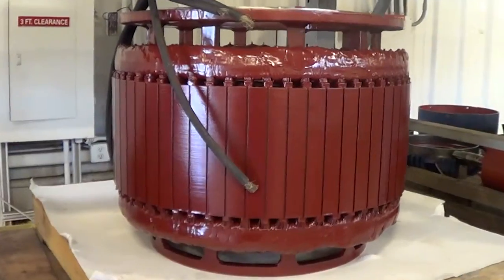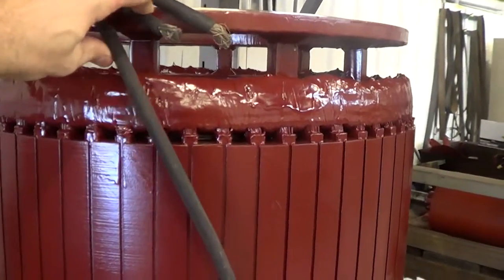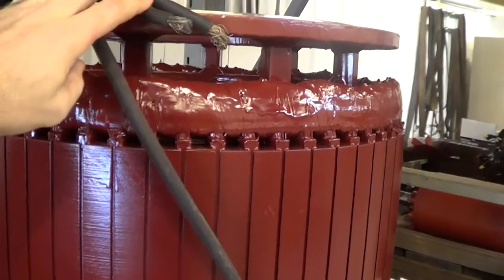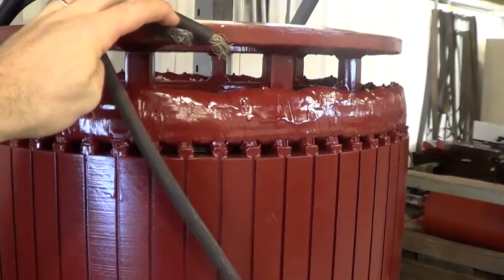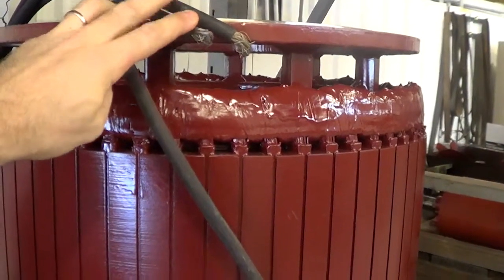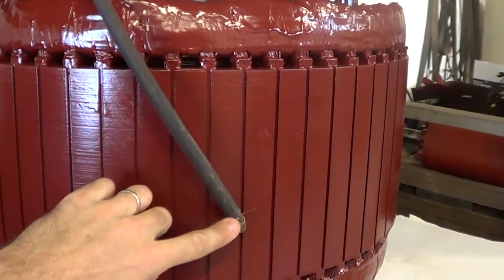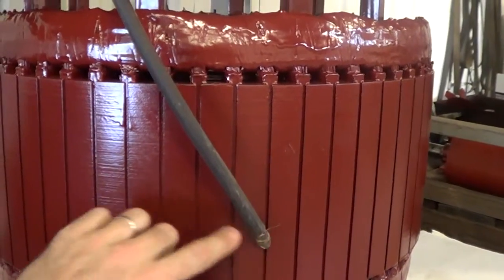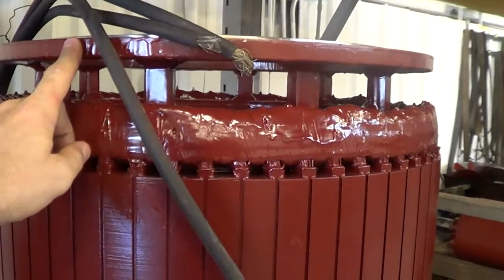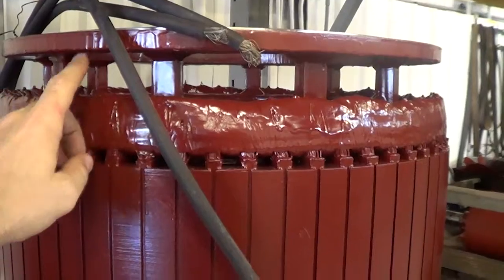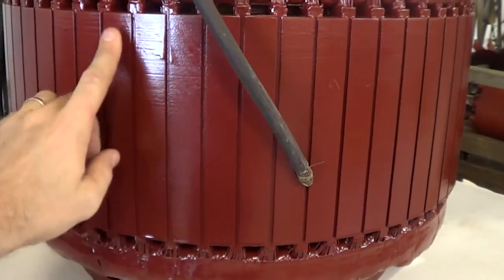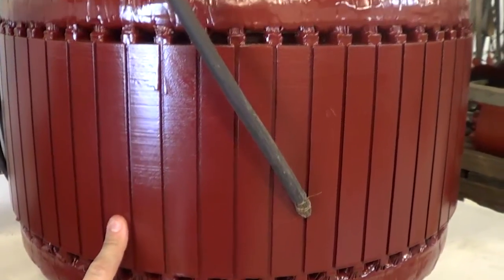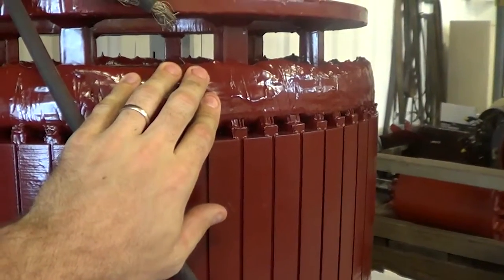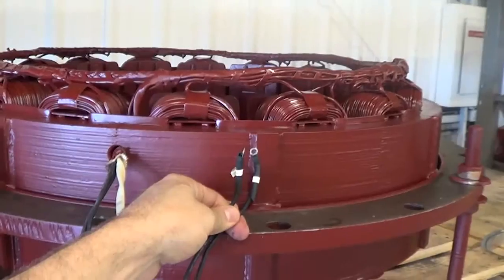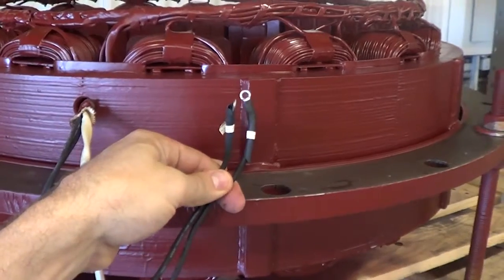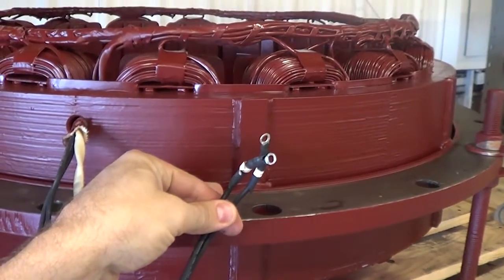The exciter rotor includes a 3-phase winding with 3 leads. Check the resistance using a digital low resistance ohm meter or micro-ohmmeter between each phase and the insulation resistance from the phase to ground, which is the shaft in the case of the exciter rotor. Visually inspect the exciter rotor for any evidence of contact along the core iron or any evidence of damage in the end turns. The exciter stator is a DC field, and so there are 2 cables.